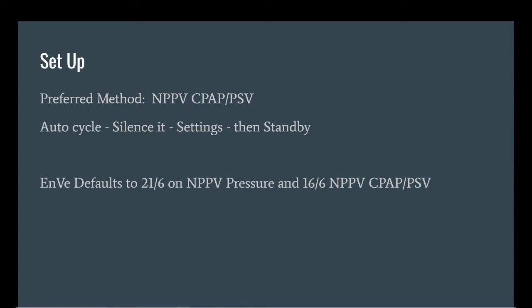The biggest thing that we don't want is to click non-invasive and ventilate, and it'll automatically start 16/6. And if your patient is, say, 8/4 or 10/5, they're going to get quite a bit of boost until you get those settings dialed in. And so that is what we want to avoid. So the preferred method is to start it, silence it, put in your settings, then put it in standby mode, wait a couple seconds, and then hit resume to then put the mask on the patient.